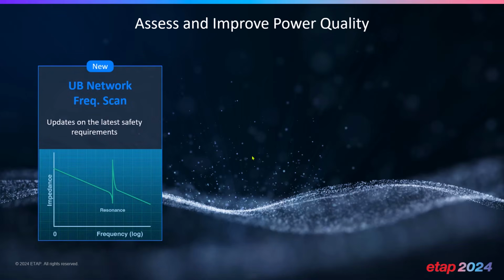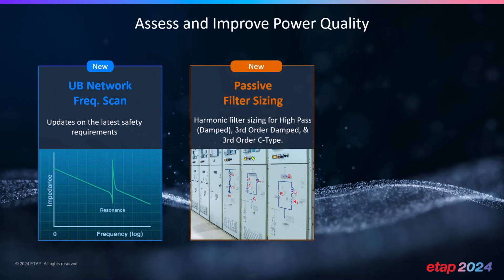You can also, of course, use ETAP to assess and improve power quality. And for this purpose, we've also enhanced our unbalanced harmonic analysis module to include unbalanced network frequency scan. And as the name suggests, it allows us to scan the frequency and plot impedance versus frequency for each phase individually, particularly useful for single phase systems. And of course, we've also enhanced the way we do our passive filter sizing by increasing our offering from not just a single tune filter, but also including sizing for high pass, third order damped, as well as the C-type filters.